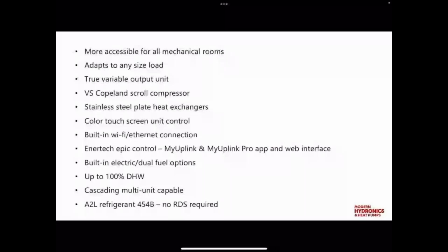So, what we've got here is a unit that is more accessible for all mechanical rooms. It is a true variable speed hydronic unit, and it's variable in every way. It's a variable output system, a fully variable inverter driven Copeland scroll compressor. This unit does feature stainless steel plate style heat exchangers. This new model has a full 5.5-inch color touchscreen on the front of the box itself. It features built-in Wi-Fi with an Ethernet port, so you can hardwire connect this unit. It does offer our Enertech Epic control and the MyUplink and MyUplink Pro app and web interfaces, which we'll go into a little bit later on.